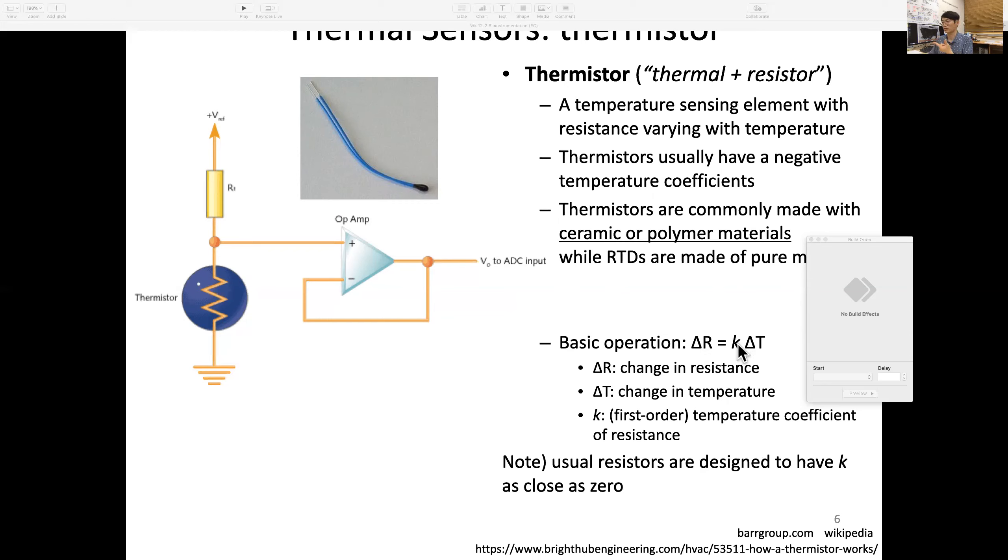Look at this data comparing RTD versus thermistor. You see much larger resistance changes, so it has higher gain or sensitivity. Also, the slope is opposite—when temperature rises, the thermistor's resistance actually goes down.